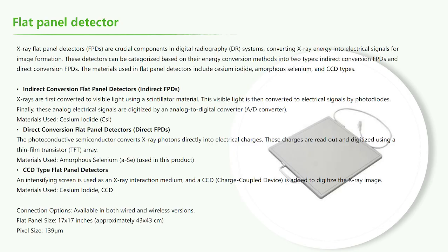The next one is the flat panel detector, also short for FPD. They are crucial components in digital radiography systems, which is also called the DR system. They convert X-ray energy into electrical signals for image formation. These detectors can be characterized based on the energy conversion methods. There are two types. One is indirect conversion, and the other one is direct conversion. The materials used in flat panel detectors include cesium iodide, amorphous selenium, and CCD.